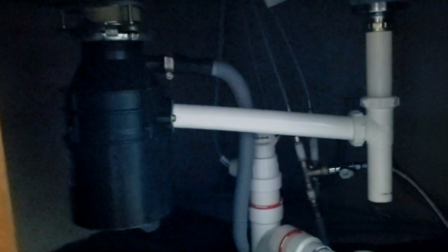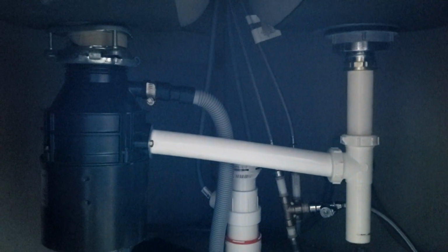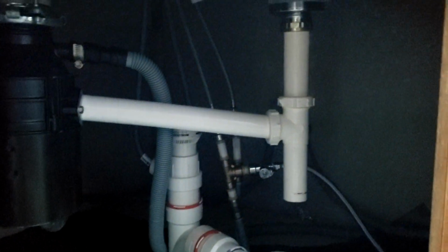This is the kitchen. Did a little electrical work in here. Totally redone the supply conduit for the disposal. Whoever remodeled this kitchen, and I believe it was 2010, must have relocated the garbage disposal to the left side rather than the right side, and they just pulled out the supply wire. So some of the Romex was just out there and it wasn't inside the conduit.